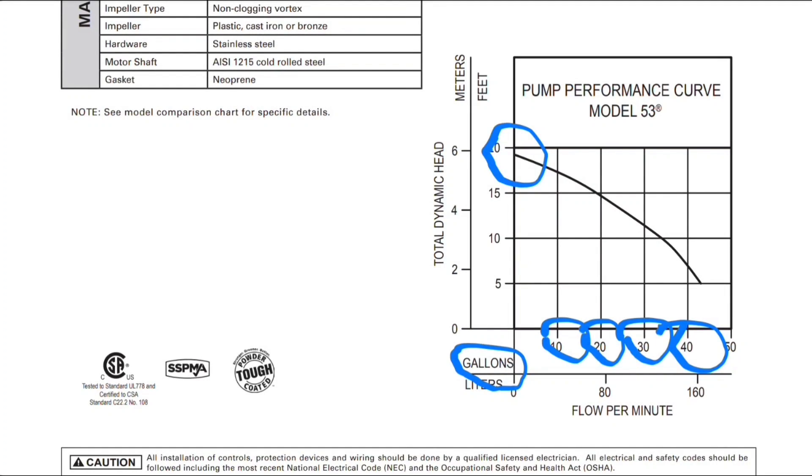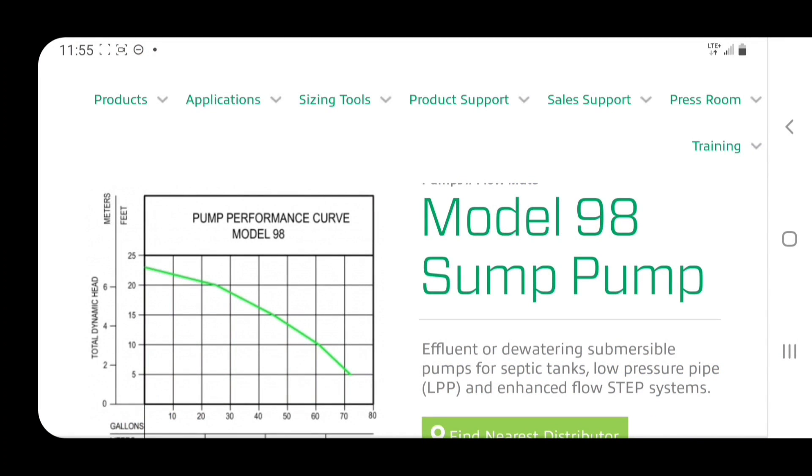Now that we know how to read these charts, let's move on to the M98 Zoeller sump pump, and I'm also going to give you a performance test — we're going to put the M53 next to the M98 in an outdoor application. Let's take a look at the graph showing the dynamic head for the M98 half-horse Zoeller sump pump. You're going to notice right off the bat this looks fantastic — 73 gallons at five feet of head. That's awesome; we're 30 gallons more than the one-third horse at five feet of head.